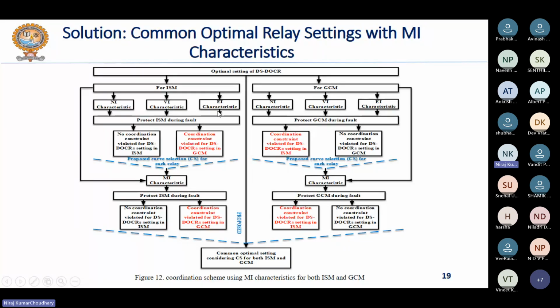So the proposed solution is that you consider these characteristics also as a decision variable while formulating the relay coordination problem, and you need to optimally determine the type of characteristics that should be used in any particular system, right? So along with the two decision variables, that is your TMS, time multiplier setting, and the other one, plug setting or current setting, this may be considered as a third optimization variable or decision variable of the relay coordination problem. And you need to use the mixed inverse characteristics, that is basically the optimal combination of NI, VI, and EI characteristics, right? So this will give you a better solution to the protection coordination problem for your system.